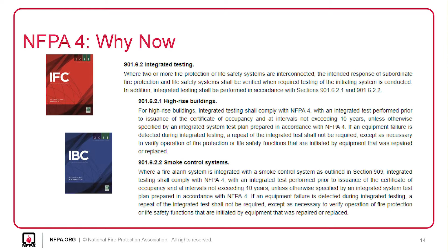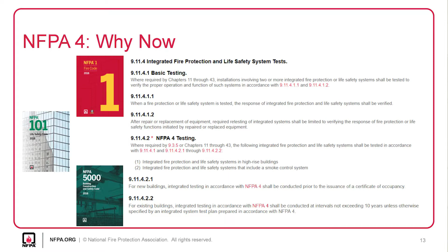So this is the other thing I wanted to get to. Prior to anything, I want to talk about where this is going. This isn't the end of integrated testing per 4 - it isn't just going to stop at high-rise buildings or buildings with smoke control systems. When the 2018 editions of these codes came out, they required testing. It just said any integrated systems within a building must be tested per 4. That is all it said.